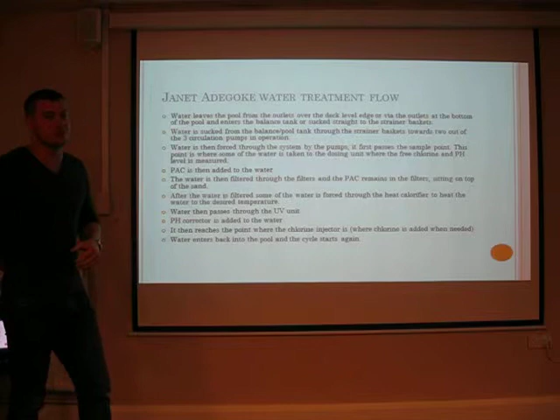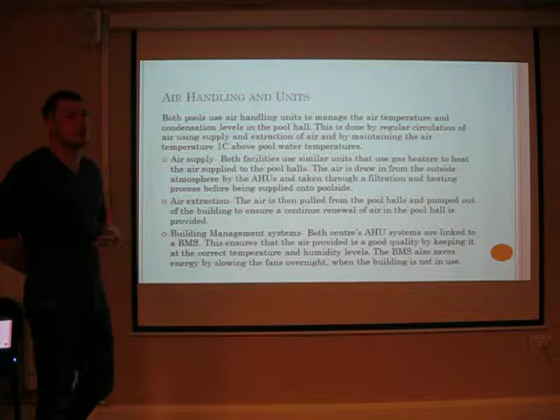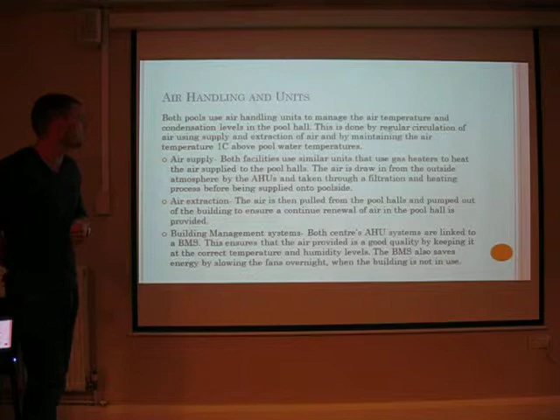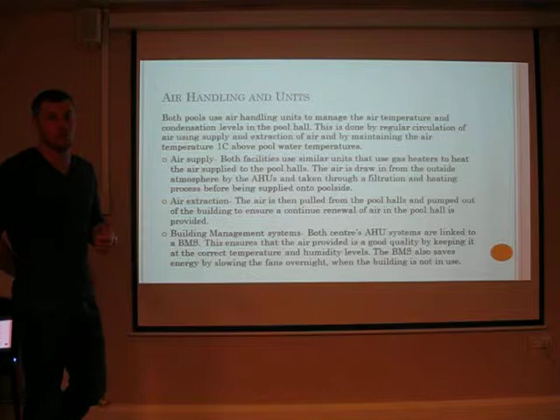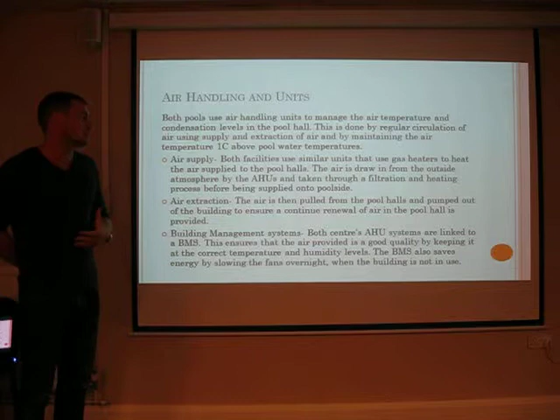Okay, air handling units at the pools. Both of them manage their air temperature with air handling units. This manages the temperature of the air and the condensation or humidity levels as well, done by regular circulation of air with supply and extraction in their pool halls. Both facilities use similar units that use gas heaters or boilers to heat their air supply to the pool halls.